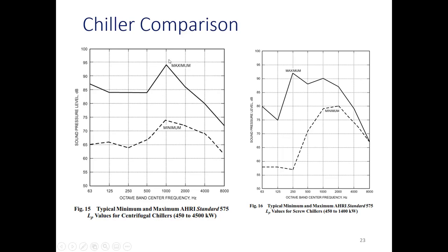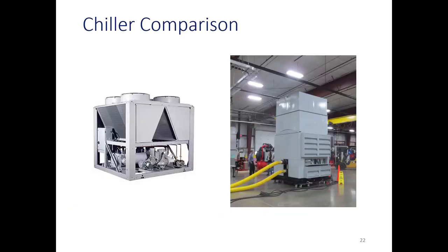And this one here is really tonal, right? It's sticking up a lot compared to the octave bands on each side. So a lot of trouble there. The maximum and the minimum: I think this is primarily based on the tonnage of cooling. Here we're seeing it in kilowatts, so we're in the metric system. I'm going to show you in tons in a minute. But I think the minimum is more this 450, and the maximum is the 4,500 kilowatts. I'm going to prove that to you in a minute. But I don't think this is so much the difference between these two, for example.